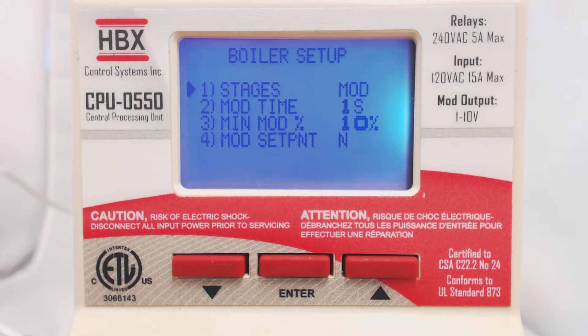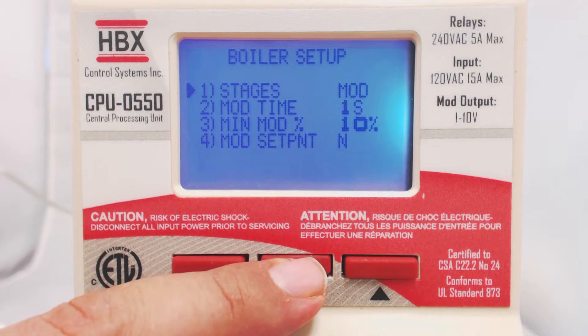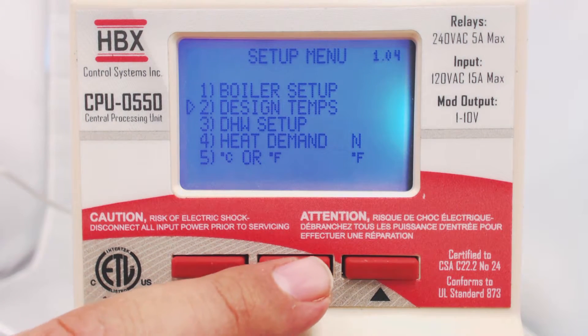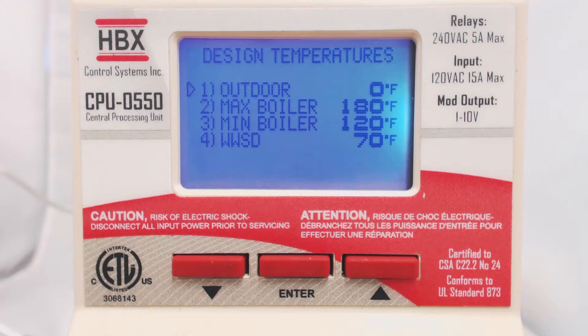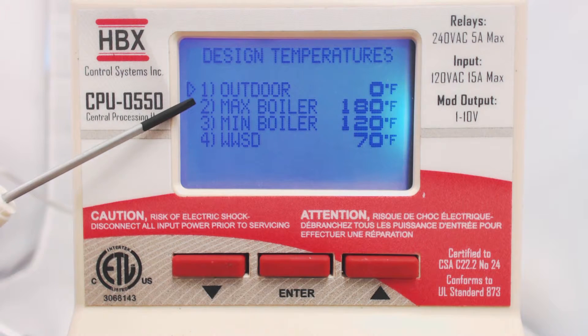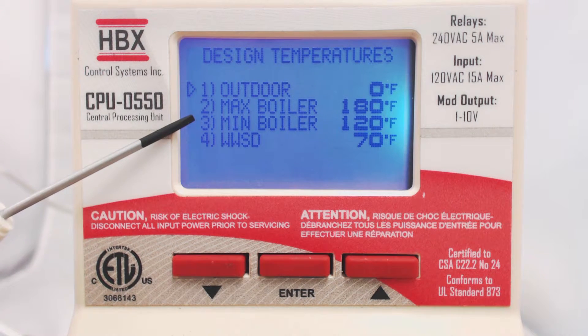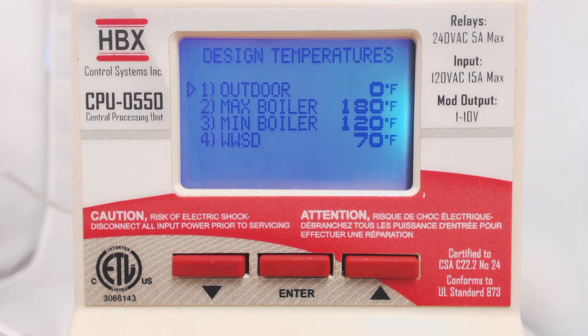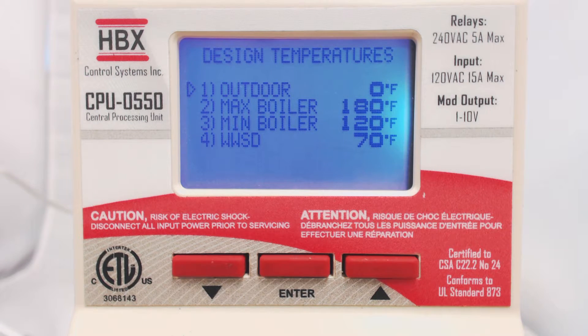To return to the Setup menu, hold the Enter button. Next, we will select Design Temperatures. This is for the Outdoor Reset curve. Here we can adjust the Design Outdoor Temperature, the Maximum Boiler Temperature, the Minimum Boiler Temperature, and the Warm Weather Shutdown. These settings will adjust the boiler target based on outdoor temperature, and will turn the system off once the outdoor temperature becomes too warm.